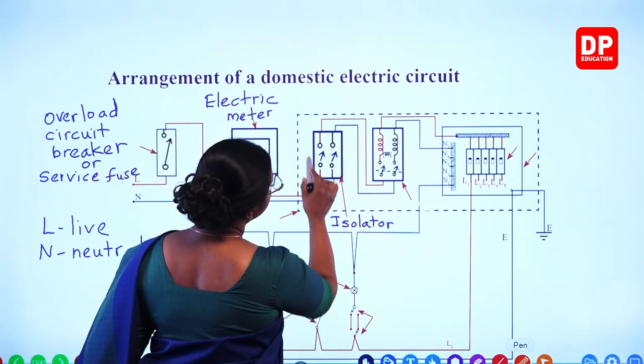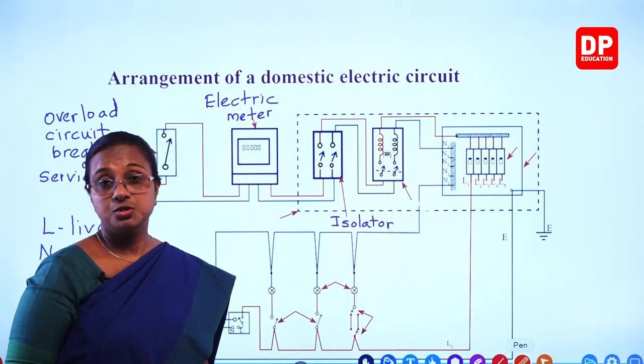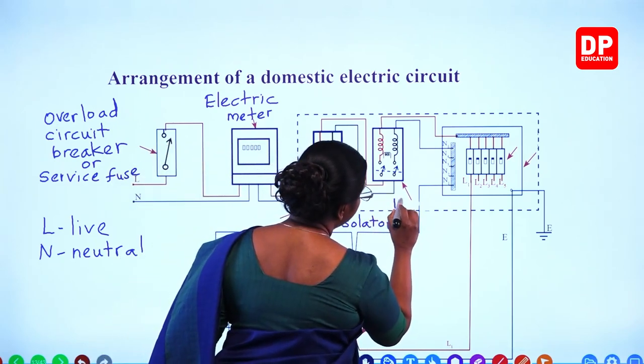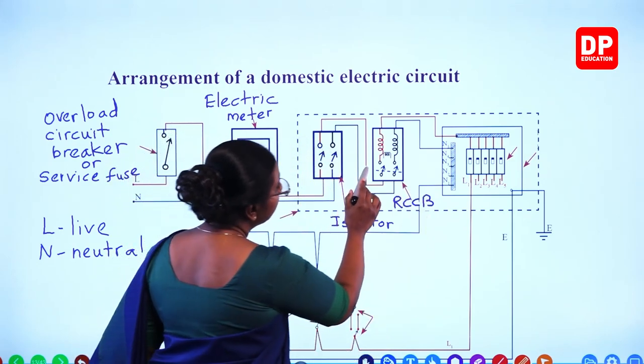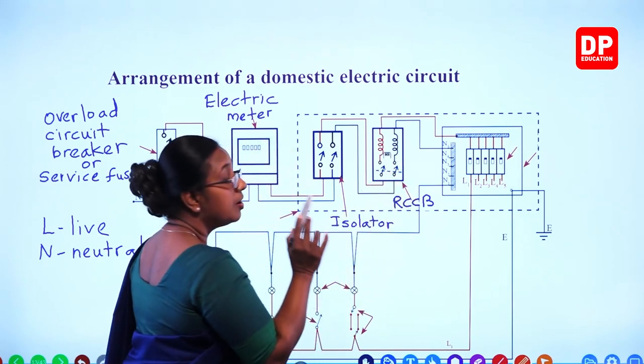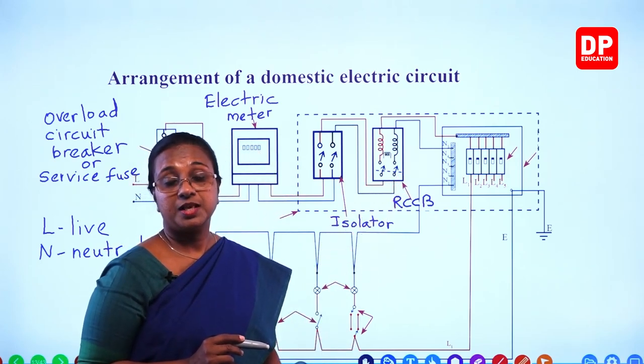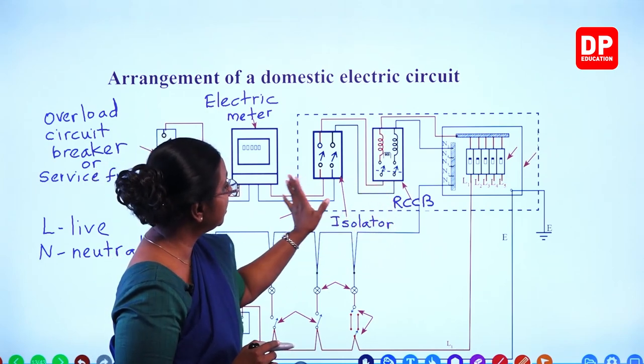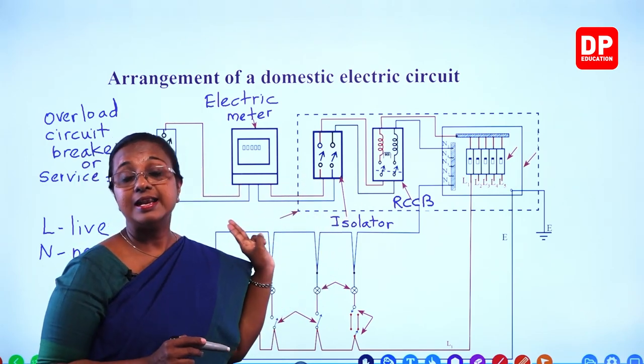From the isolator, the wire connection goes to the next component: the trip switch or RCCB — residual current circuit breaker. Here also, both the brown live wire and blue neutral wire are connected, and both can be disconnected by the trip switch. So the isolator and RCCB are both dual pole switches, which disconnect both live and neutral wires simultaneously — different from the overload circuit breaker.